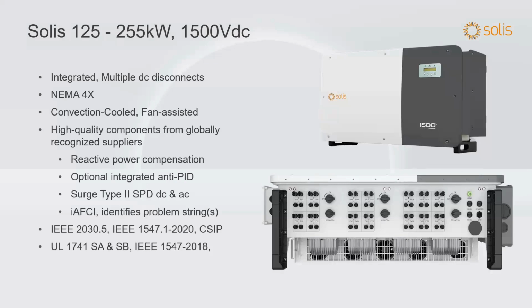Just an interesting thing, but I wanted to tell you that you've got 3 other options. You can remove that gray cover and tie into the board directly using a Cat5 cable - there's RJ45 jacks right on the COM board. There's also terminals for a Belden type cable, solid core, 22 or 24 gauge, something like that. If you really want to carry data for a long distance, that's a nice way to go. And then the PLC, that's another nice way to go. So, 4 ways to get the data off of these inverters.